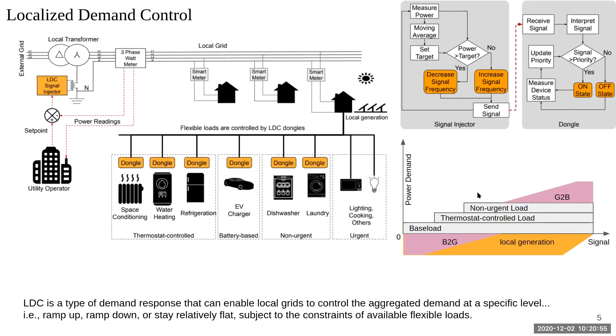So if we look at this graph here, if we increase the signal frequency, we have different types of devices here. As we increase the command signal, different types of devices would turn on. And we have the special case for battery. So you have grid to battery. That means the battery would charge, but if the signal is lower than its set priority, it will discharge. Meanwhile, for the local generation, there's a certain threshold wherein it will start to reduce its output. This is to avoid the reverse power flow.